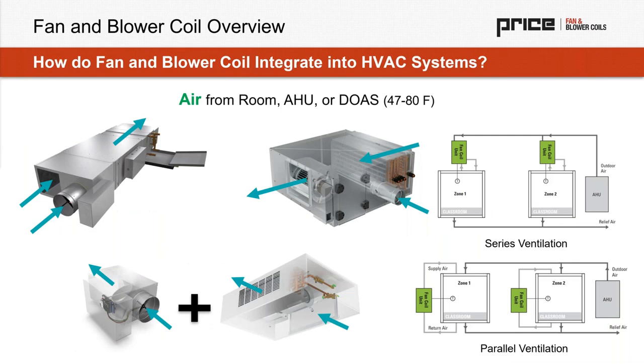So when we look at how these products actually integrate into HVAC systems, there's really two ways to look at it. It's the air side and then the water side. So starting with the air side here, there's two main ways that these integrate into the ducted system. The first, which we can see on the top of the screen, would be series ventilation. So the methodology there is, let's actually add our outdoor air directly into the fan coil and have a single path for supply air to enter the space through air outlets.